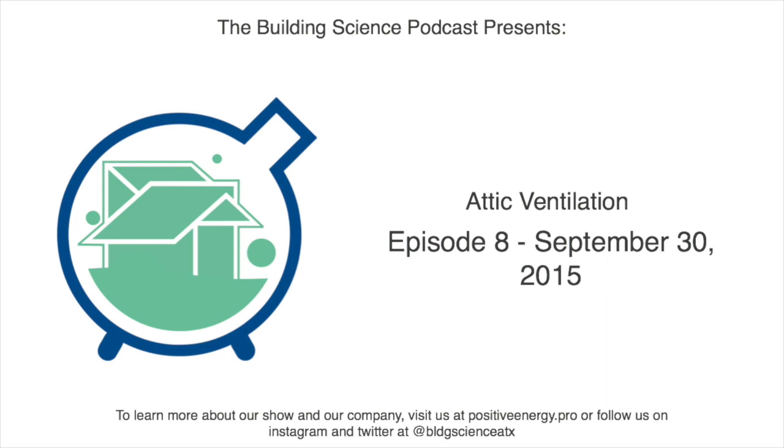Bill Rose had the same result, and even earlier in the late 90s, Armin Rudd and Joe Lstiburek, actually in hot humid climates, they point out that attic ventilation is not only a bad idea, it's one of the leading causes of moisture problems. And that's actually the motivation for this podcast, was a consultation we had last week with a powered ventilator assisted attic with just tremendous humidity problems inside the house, inside the attic. And not just humidity, but comfort problems, indoor air quality issues.